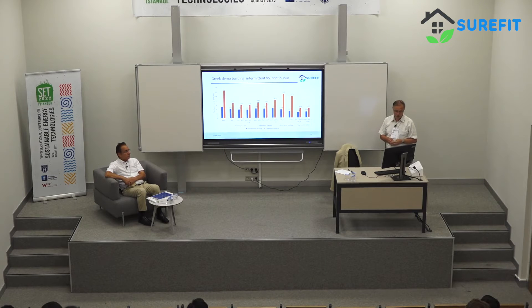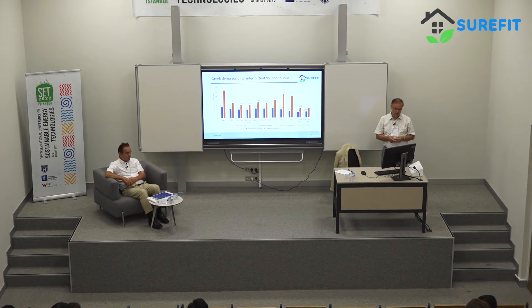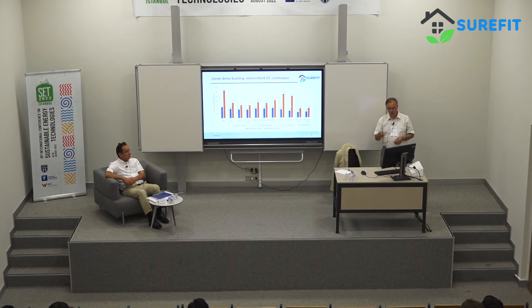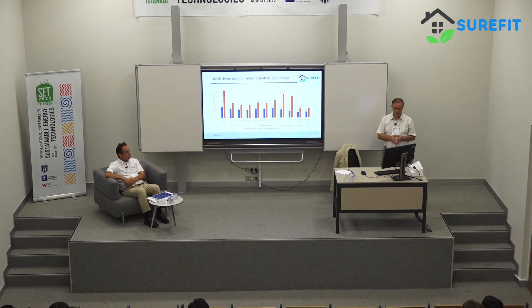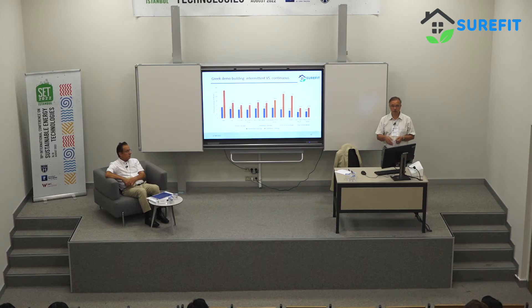Here we have two different parts: the blue one is intermittent heating and the other is continuous heating. Looking at passive measures, for example insulation has only a 16% reduction in energy consumption under intermittent heating, but 44% under continuous heating. For the generation package, in continuous heating efficiency is lower — 14% or 22% — but in actual cases with intermittent heating the effect is higher. Simplifying the results: in continuous heating, passive measures are relatively more effective than energy generation.